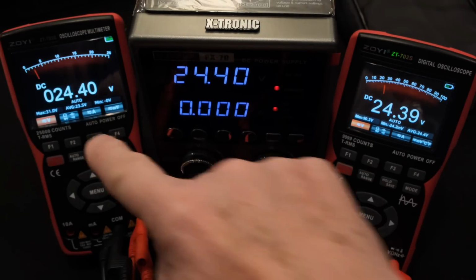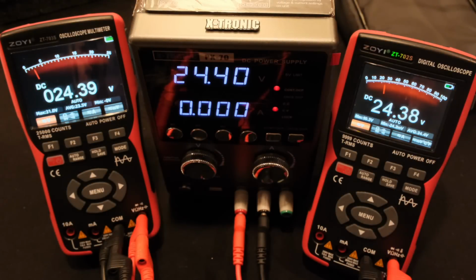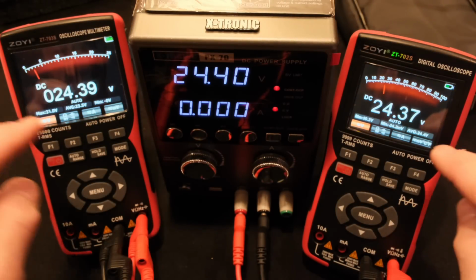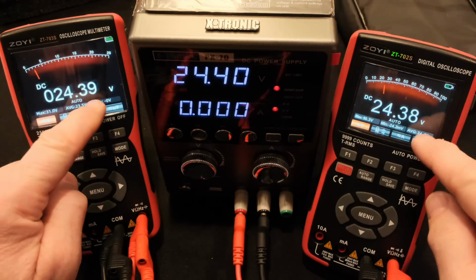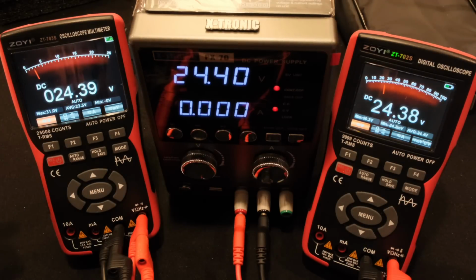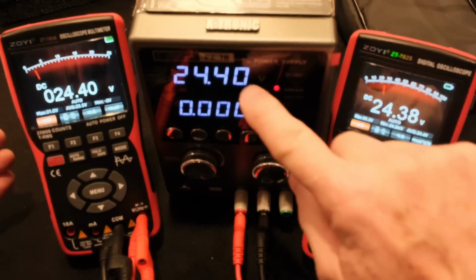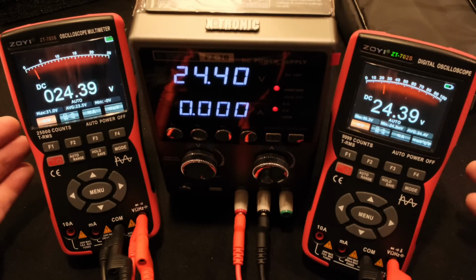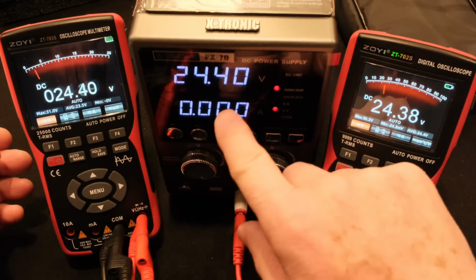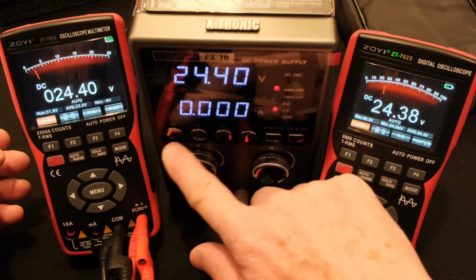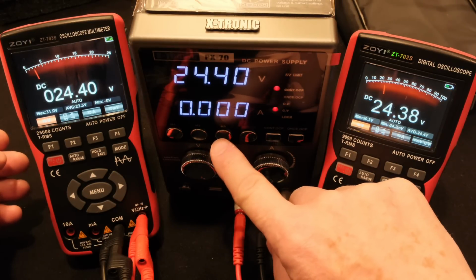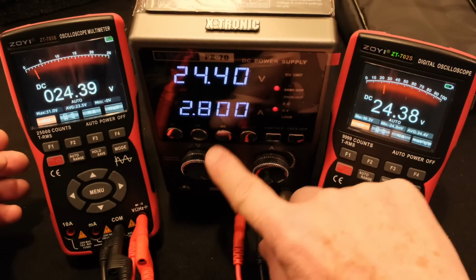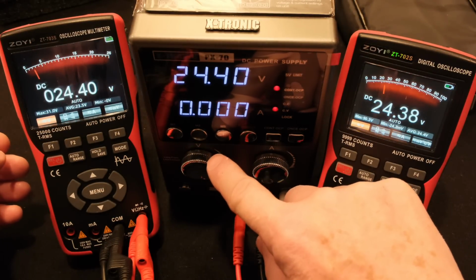And this one is 0.5%, so 10 times better over here. 0.5%, 3 counts, 0.05. So there we go. The last digit can be 3 counts off, right, plus the tolerance. So anyway, it looks pretty darn close. They're all hitting just about right. Now this is the X-Tronic power supply. It has 3 programmable outputs, and that's M3, I think. Yep, that's the third programmed output.